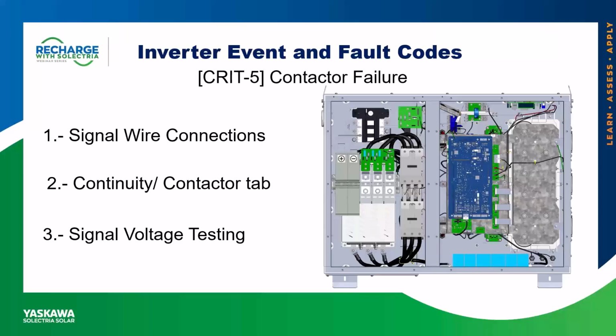You can power cycle the inverter, and once the unit has finished its 5-minute countdown, like I mentioned, the digital signal processing board is going to fire a 24 volt DC signal voltage to the contactors to allow them to engage. So if you test after you've power cycled the unit, on the top contactor, K2, that's typically the one that will engage first, always. After the top one has closed in, the bottom one, K1, is the one that closes in.